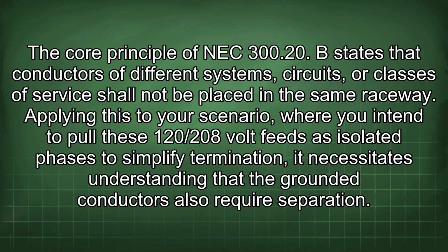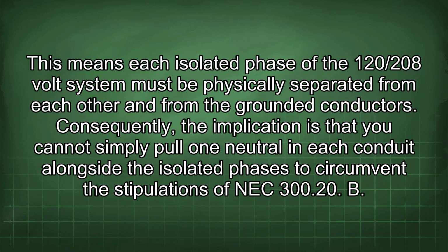Applying this to your scenario, where you intend to pull these 120/208 volt feeds as isolated phases to simplify termination, it necessitates understanding that the grounded conductors also require separation. This means each isolated phase of the 120/208 volt system must be physically separated from each other and from the grounded conductors. Consequently, the implication is that you cannot simply pull one neutral in each conduit alongside the isolated phases to circumvent the stipulations of NEC 300.20.